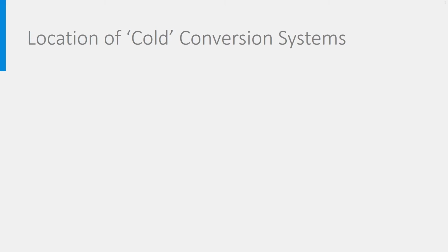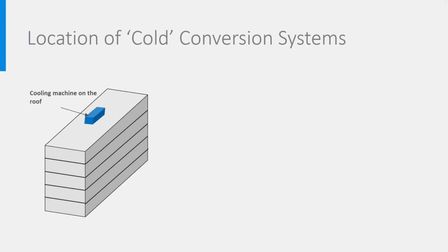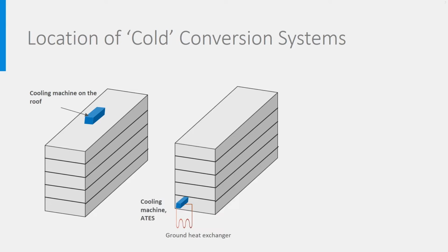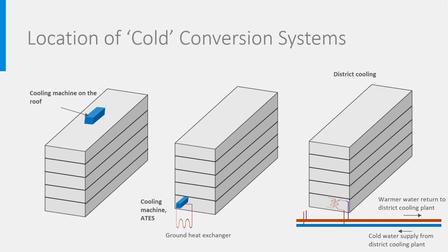Let's start with the cold conversion system. Those are chillers, also called cooling machines, which are in fact heat pumps in reverse mode, or ATES systems, aquifer thermal energy storage systems, or systems using surface water like sea or river. No combustibles are used, so it does not matter very much what the location is. In general, a central place on the roof or in the basement will be chosen. Sometimes there are also cooling district networks delivering cold obtained by an absorption heat pump elsewhere.